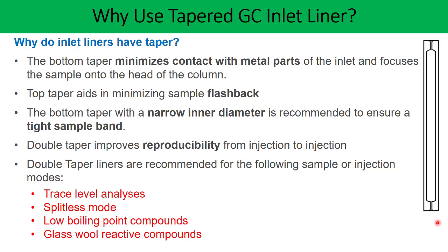Glass wool is also a very effective tool to increase vaporization and homogenization of the entire sample vapor. However, if a compound reacts with the glass wool, you may not be able to use it. In the absence of glass wool, there may be a chance of lower injection-to-injection consistency and the sample may sometimes not get completely vaporized. To avoid this, you can use double tapered glass inlet liners. Please let me know in the comments if you know any other reason why you must consider using tapered glass inlet liners. Thank you so much.